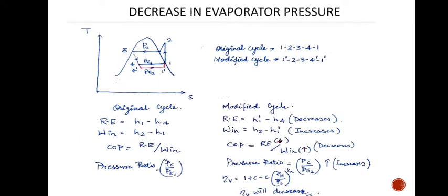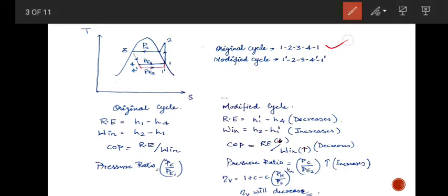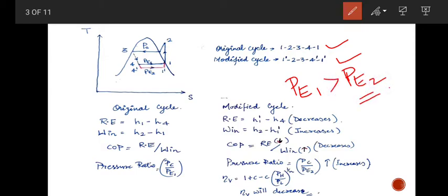The first point is decrease in evaporator pressure. If we decrease the evaporator pressure, what effect on our cycle will occur? The original cycle is 1-2-3-4-1 and the modified cycle is marked in red as 1'-2'-3-4'-1'. In this case the pressure decreases from Pe1 to Pe2. For the original cycle, the refrigerating effect is H1 minus H4, and for the modified cycle it will be H1' minus H4'.